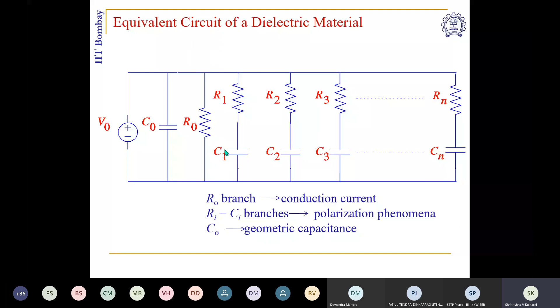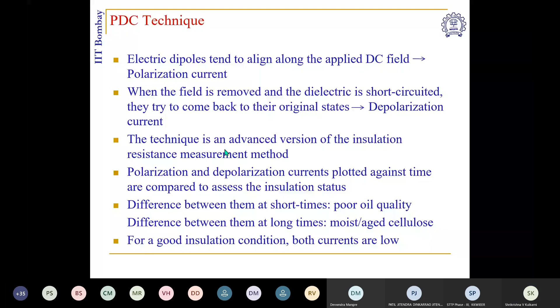Now, what is this polarization and depolarization technique? Basically, electric dipoles tend to align along the applied field because of the polarization phenomenon, and then they get depolarized, trying to come back to the original state when the field is removed and the dielectric is short-circuited. The polarization and depolarization currents are plotted against time, and they are used as diagnostic indicators. The difference between polarization and depolarization currents at short times is indicative of poor oil quality, whereas their difference at long times is indicative of moisture or aged condition. And for a good insulation condition, both the currents should be low, overall, and the final steady state current should be low.